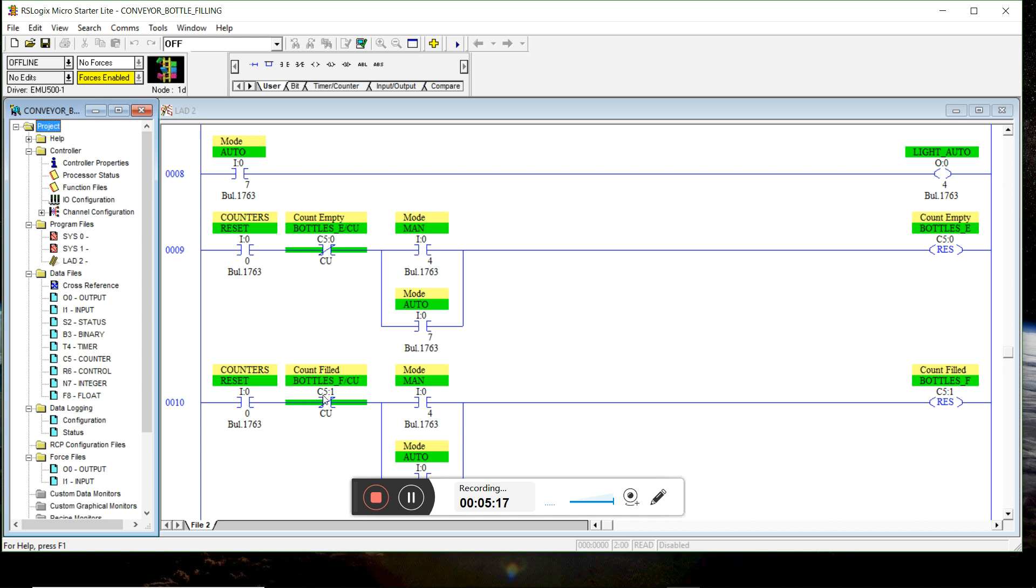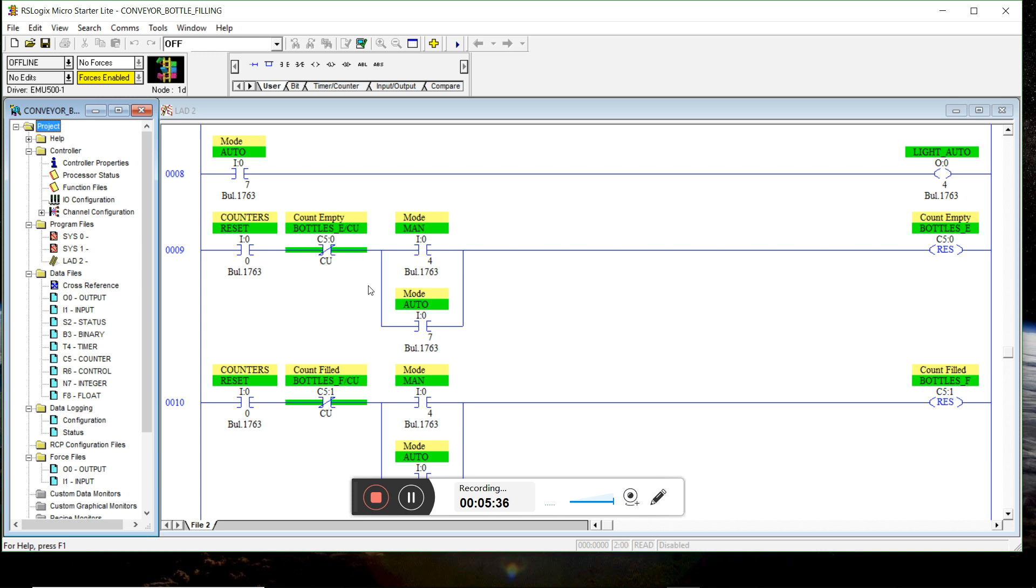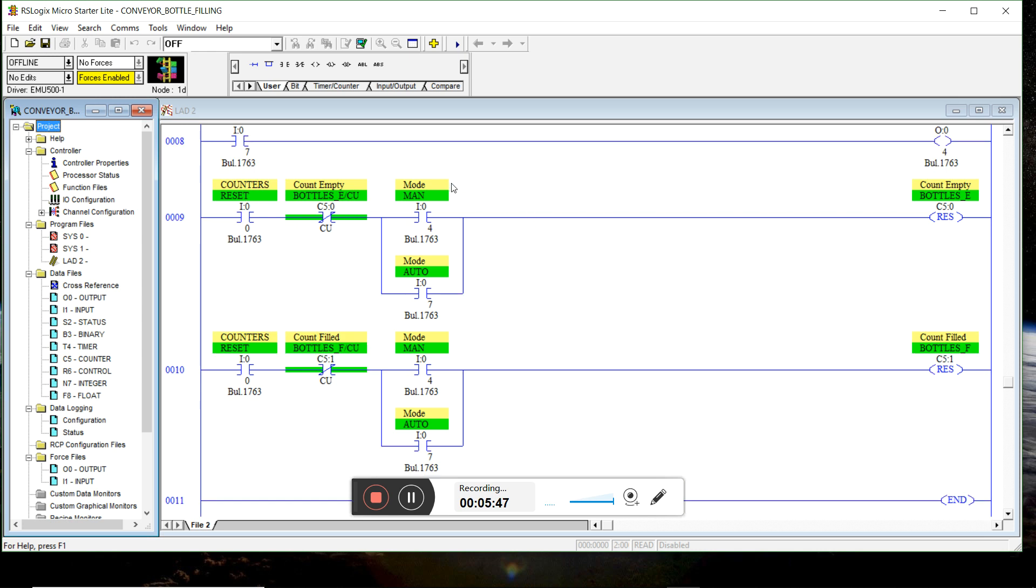This will ensure that we won't count the same bottle twice. So if the photo eye is blocked and we hit the reset button, it goes to zero, but it's gonna count one again because the photo eye is blocked. So this ensures that it doesn't do that. When you press the momentary push button when the photo eye is blocked or when you're counting, you're not gonna be able to reset it. And we can reset both in manual and in auto mode.